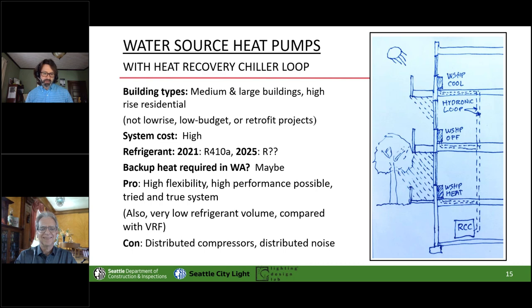You know, we're talking 20 and 30 years, or 30 and 40 years ago now. You do a water source heat pump loop. You'd have a little cooling tower and you'd have a fairly sizable boiler, and great. It was like VRF before VRF, because you got to share heat around the building on a water loop.